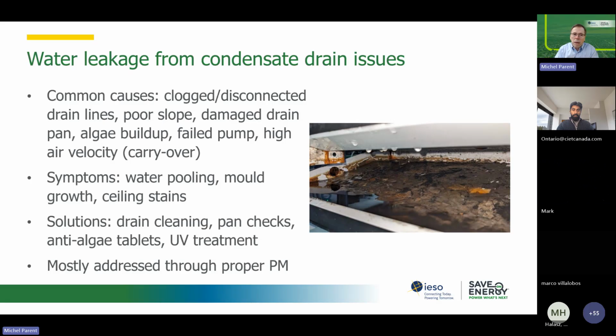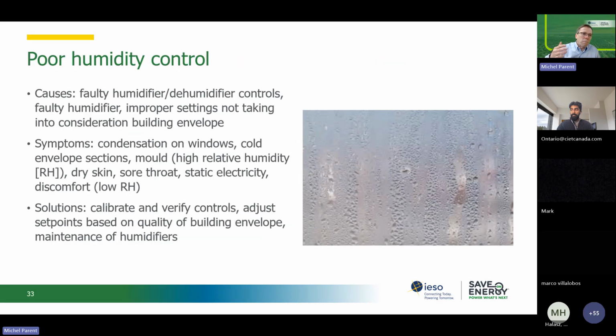Make sure that part of the PM is not only to clean the drain, but to verify that there are no signs of condensate accumulation anywhere. If your humidifier is over humidifying, or your humidity sensor on the discharge is not reading properly, you may create puddles in your ductwork because of over humidification, because of one bad sensor. That would be your high limit sensor, which is similar to what we see here poor humidity control.